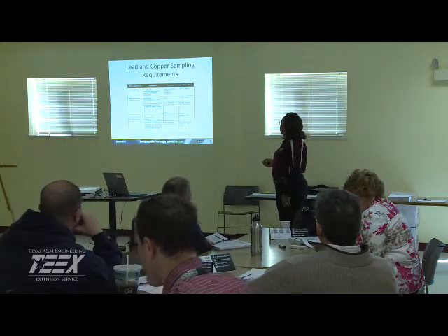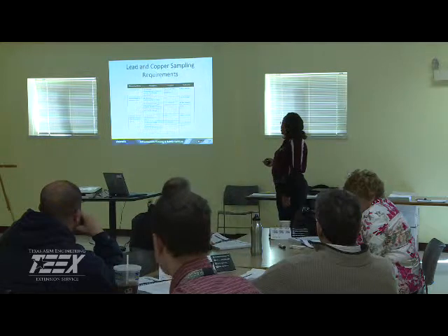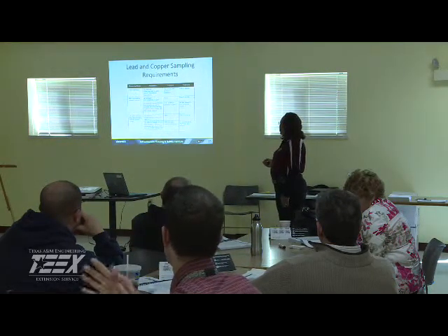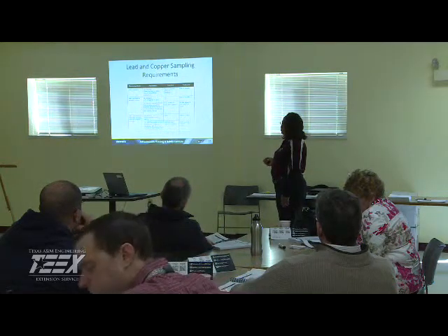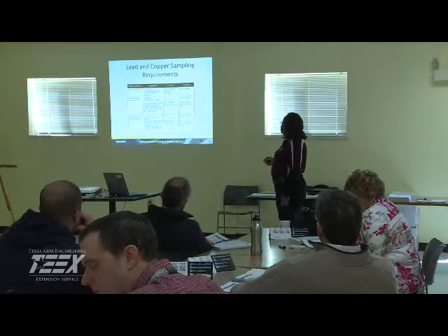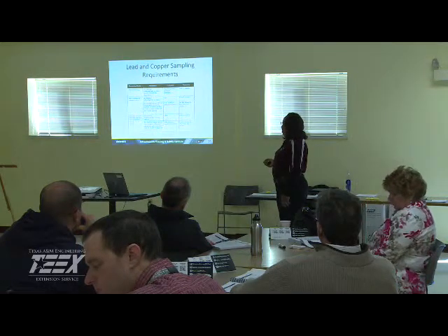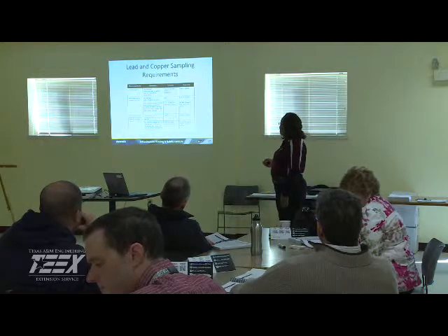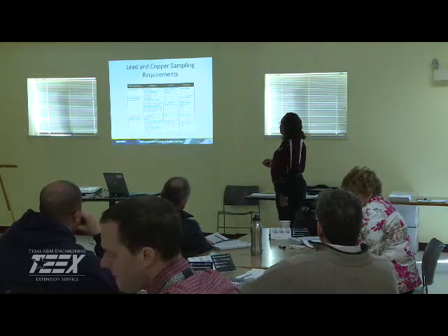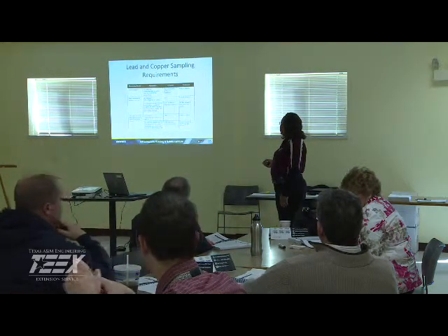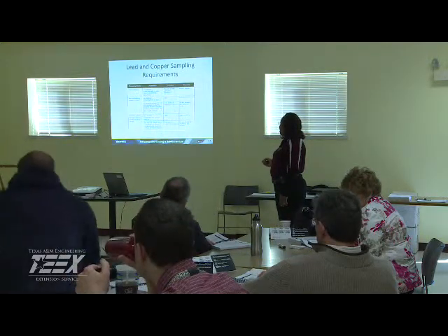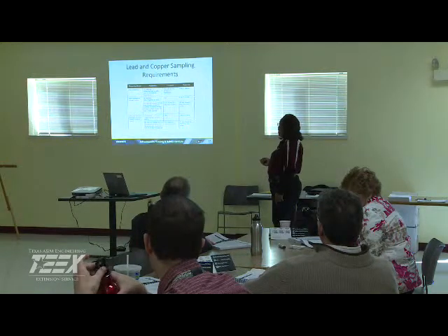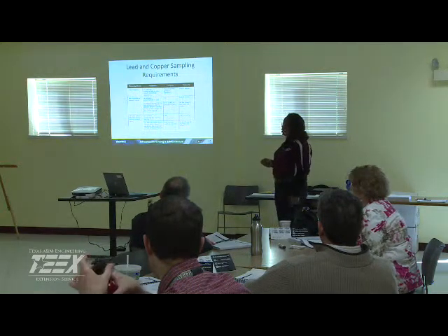After installation of corrosion control, we're still looking at pH, alkalinity, orthophosphate or silica, if applicable. We're going to do those at the taps, and we're going to continue with every 6 months. We're also going to do pH, alkalinity, dosage rate, concentration, inhibitor dose rate, inhibitor residual at every entry point to the distribution system, and this should be completed no less frequently than every 2 weeks.